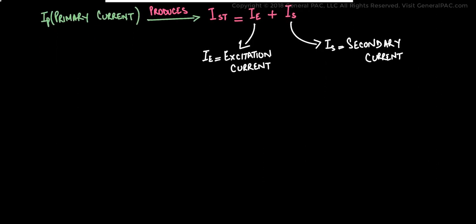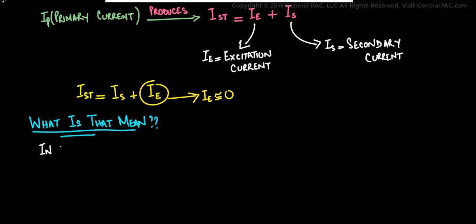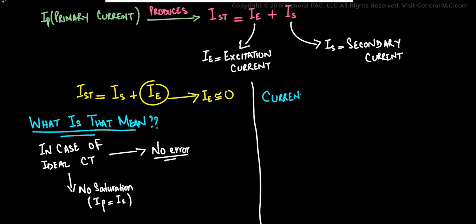The total secondary current as shown by IST is equal to the secondary current only when IE is equal to zero. Now what does that mean? What we are trying to say here is that if we model an ideal current transformer where there is no error or there is no saturation, where the primary current is equal to the secondary current. In this case, we are saying that IE is zero and IST is equal to IS.